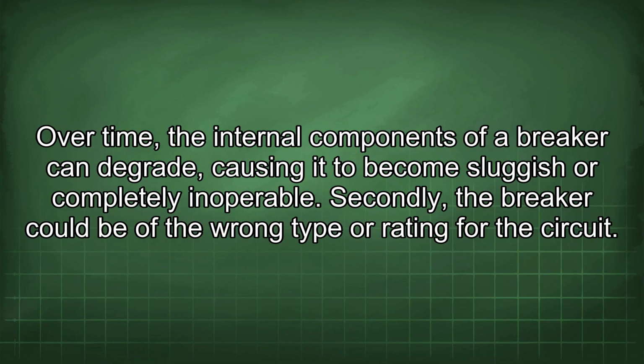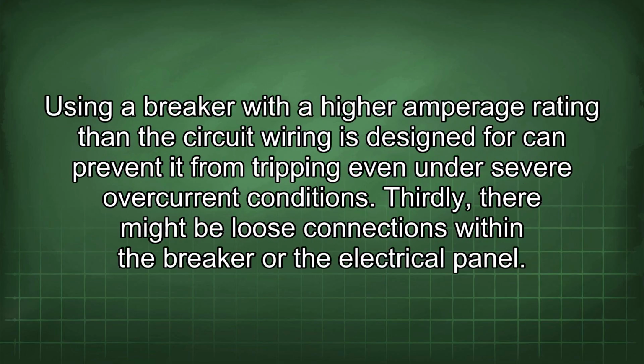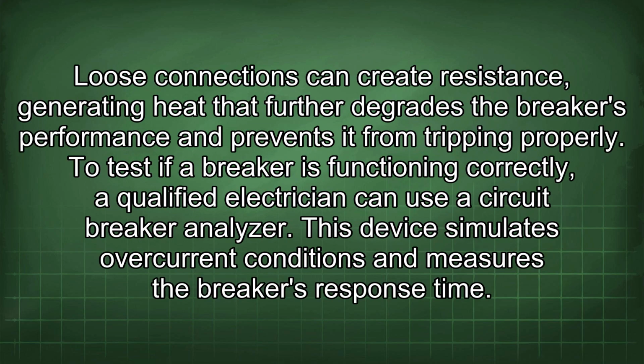Secondly, the breaker could be of the wrong type or rating for the circuit. Using a breaker with a higher amperage rating than the circuit wiring is designed for can prevent it from tripping even under severe overcurrent conditions. Thirdly, there might be loose connections within the breaker or the electrical panel. Loose connections can create resistance, generating heat that further degrades the breaker's performance and prevents it from tripping properly.